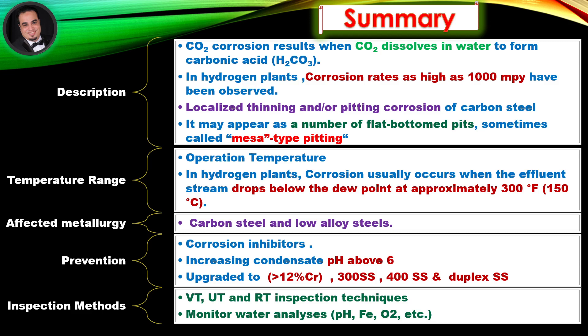Affected metallurgy: Carbon steel and low alloy steels. Prevention: Corrosion inhibitors, increasing condensate pH above 6, upgrading to more than 12% chromium, 300 and 400 series and duplex stainless steel. Inspection methods: VT, UT, and RT. Monitor water analyses: pH, Fe, O2, etc.